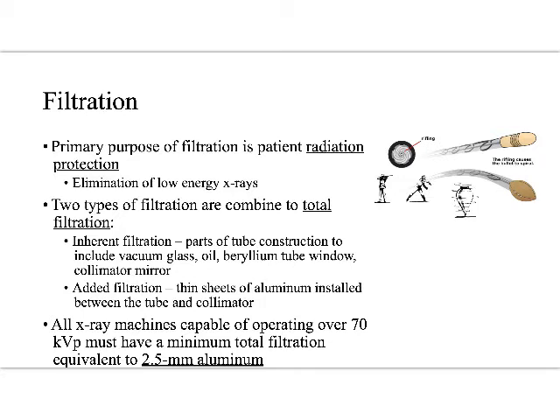You'll see all sorts of distracting questions about filtration, and hopefully you'll remember: it is just for radiation protection. There are two types of filtration combined to form total filtration. Inherent filtration comes from the parts of the tube itself — the oil, the beryllium window, the collimator mirror — all of which can filter out weak x-rays. That's inherent because it's part of the way the machine is designed and built.